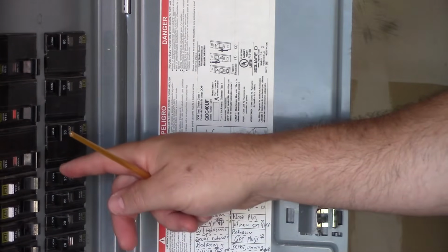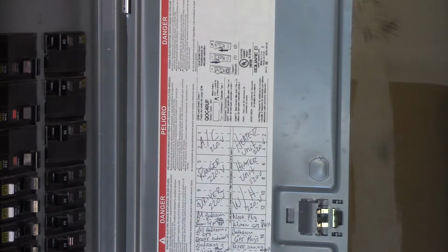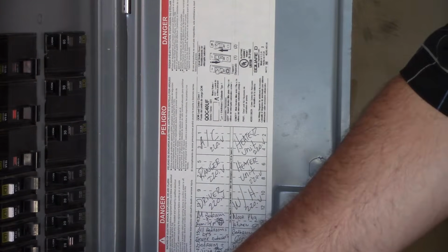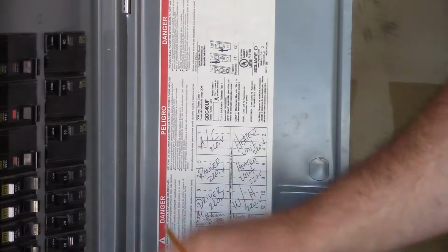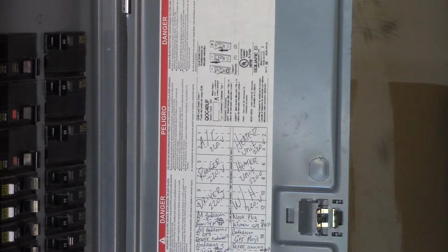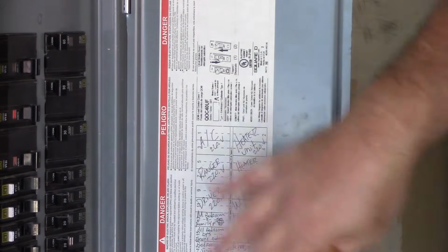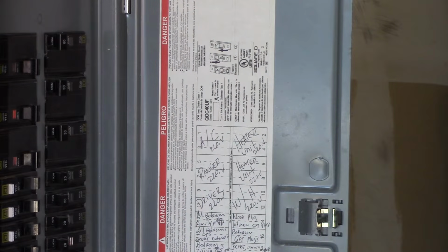None of the breakers are damaged, cracked, any signs of deformation in the plastic. Anything that's going to stand out of the ordinary, you want to look at. And so everything looks good here. All the breakers seem to be seated pretty good. So the main breaker's seated well. So there's really nothing else in here that I'm too overly concerned with. The legend, the directory, I guess, looks pretty good in this panel cover.